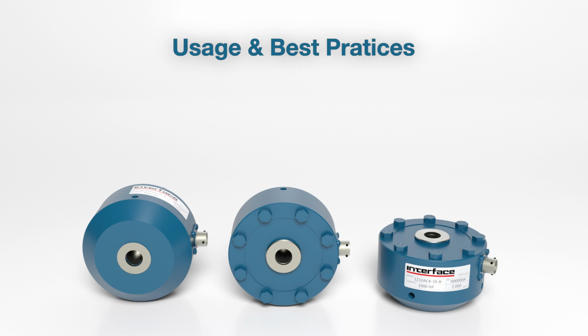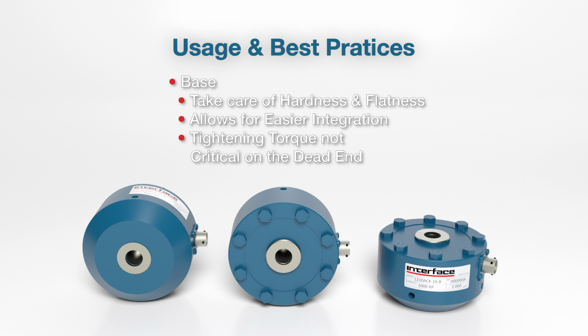So talking about bases, bases are a very convenient way to basically get the same performance out of your application that we get on the cal frames. Again, we calibrate on bases. If you get a base with your load cell, you won't have to worry about all those plate details and making sure things are flat and hard, and it's a lot easier to integrate into your assembly. You end up with a female threaded hole on the top and a female threaded hole on the bottom. Works really well for, again, using them inline on hydraulic actuators and such like that. So typically we recommend customers go with bases if possible. Just makes things typically easier in the end run.